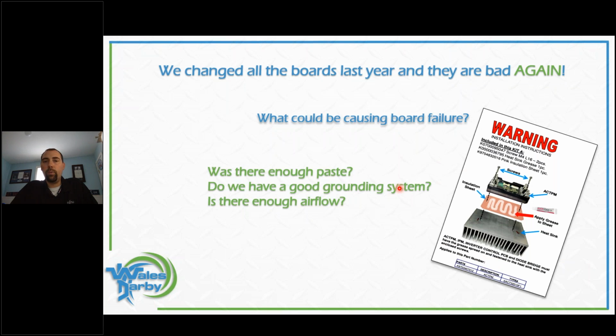All right, so we changed all the boards last year, and they're bad again. That's something I've heard a couple times. We keep constantly having to do boards, right? We've done multiple boards, and they just keep coming back. What causes board failure? Well, maybe the first guy that did it didn't really use the paste. He didn't tighten it down all the way.